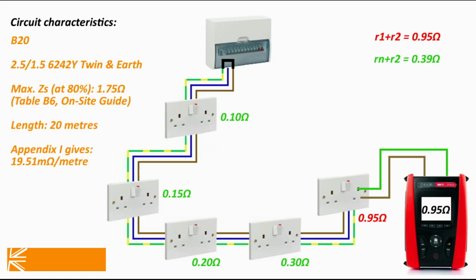So anyway, what if all this resistance testing identifies there is a fault? On our circuit, perhaps we're getting 0.95 line to CPC, 0.39 neutral to CPC. That lower number suggests the CPC and neutral are where they should be, that the circuit length is 20 metres, which appears sensible based on the proximity of the accessories to the consumer unit in this example. So we can determine we have a high reading on the line. Arcing isn't going to occur over a resistive fault this low, but if a loose connection is present, it's likely to worsen over time until it starts going open circuit, where the trouble will really begin.